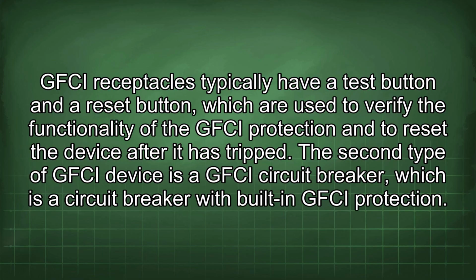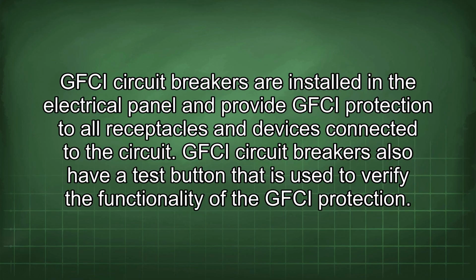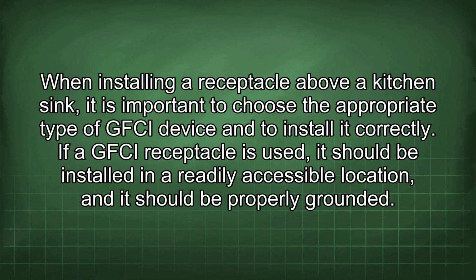The second type of GFCI device is a GFCI circuit breaker, which is a circuit breaker with built-in GFCI protection. GFCI circuit breakers are installed in the electrical panel and provide GFCI protection to all receptacles and devices connected to the circuit. GFCI circuit breakers also have a test button that is used to verify the functionality of the GFCI protection. When installing a receptacle above a kitchen sink, it is important to choose the appropriate type of GFCI device and to install it correctly.